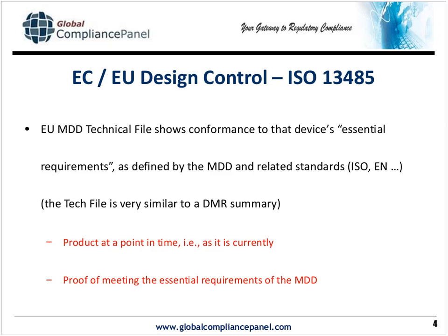So whenever you change your product, you have to upgrade your technical file / design dossier. That's different from the FDA's design history file, which shows the development history up to at least design transfer, if not all the way through to cradle to grave, so to speak. So there is a difference between technical file design dossier and the design history file, although the majority of the documentation will overlap. The design history file will in fact be larger in most cases, with many more pointers to other documents like validation documents, as opposed to a technical file design dossier.